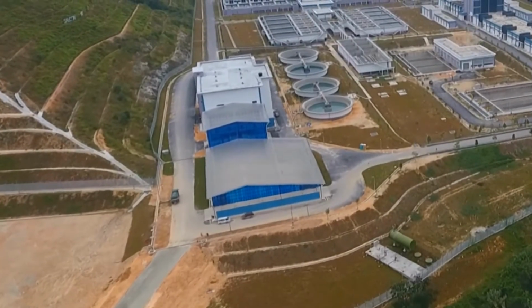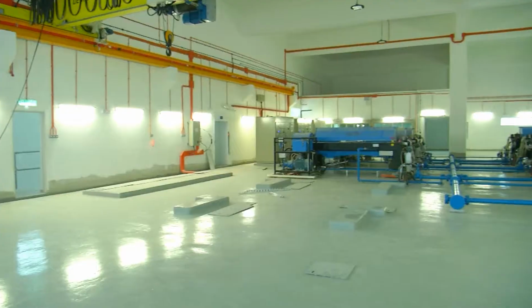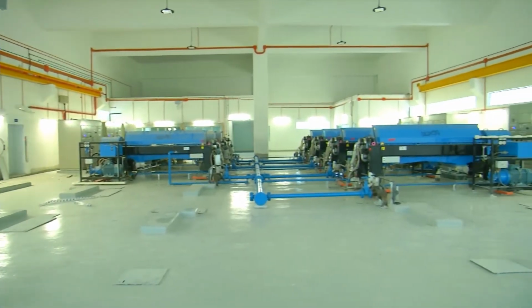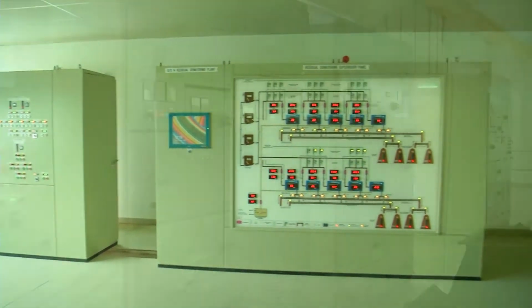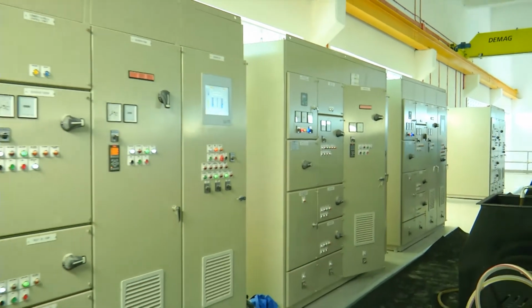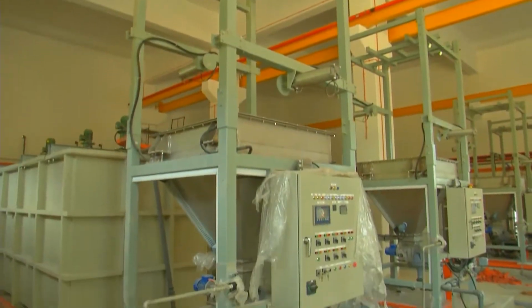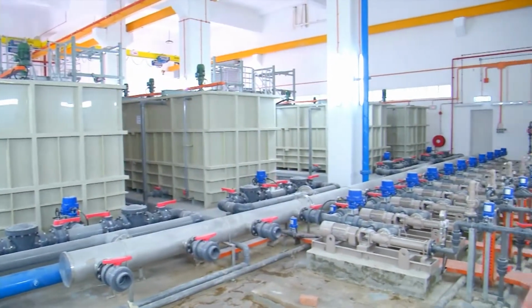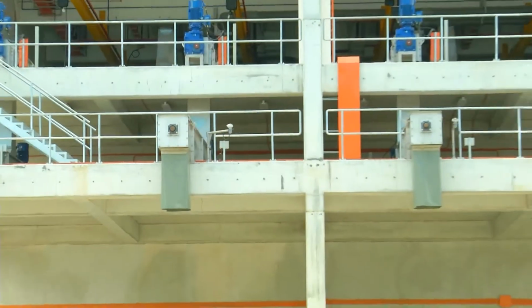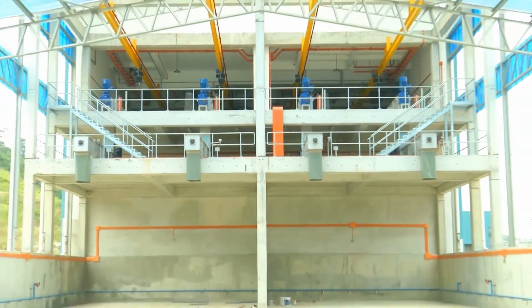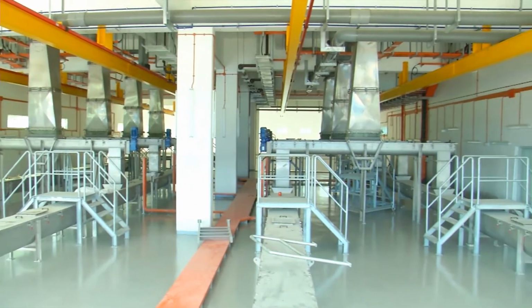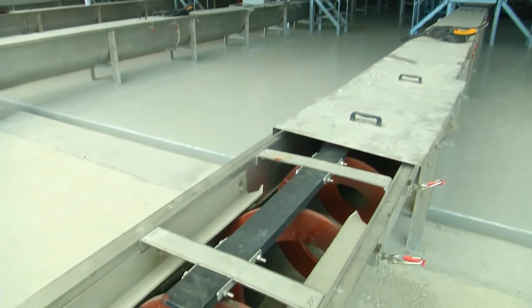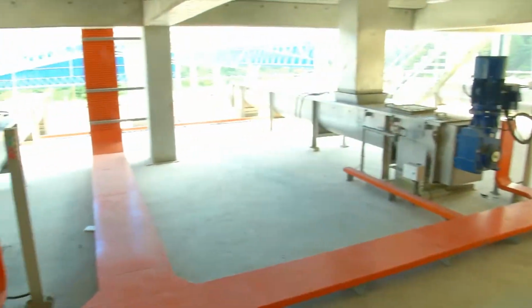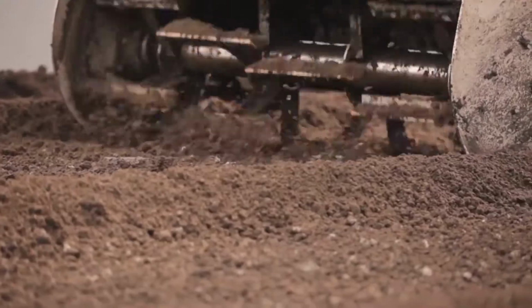Dewatering plant and storage yard. The dewatering process uses centrifuge decanters. The dewatering plant is constructed to cater for sludge production from Phase 1 and Phase 2 of the water treatment plant. Polymer is dosed again to facilitate the dewatering process. Dewatered sludge is then discharged and collected at the storage yard via screw conveyors. Dried sludge is then ready for onward transportation to landfill.